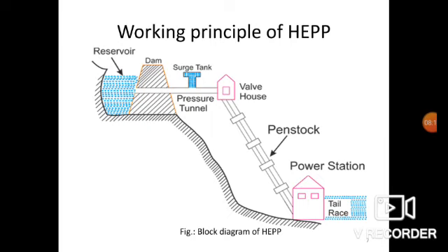A pressure tunnel is placed between the reservoir and the valve house, and water comes from the reservoir to the penstock through this tunnel. An automatic controlling switch gate is placed in the valve house to control water flow to the power station and to cut off supply of water in case the penstock bursts. The penstock is a huge steel pipe in which water is taken from the valve house to the turbine. A surge tank is also provided just before the valve house for better regulation of water pressure in the system.